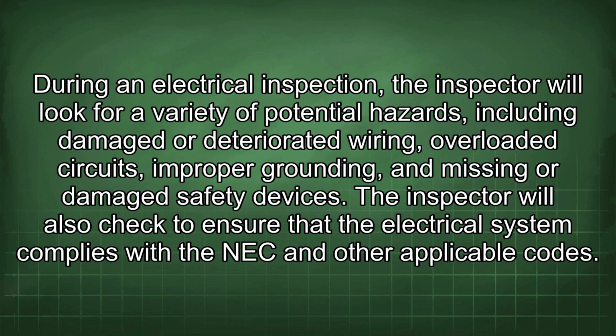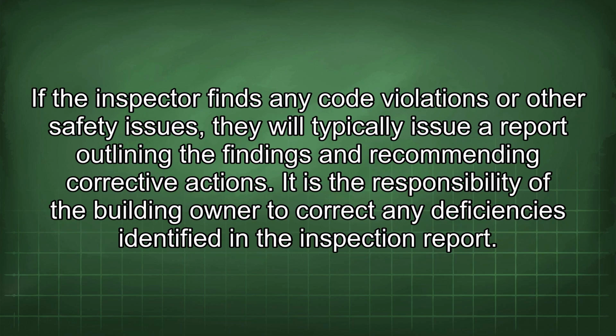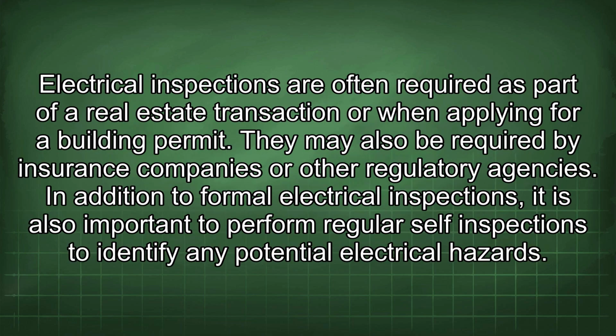During an electrical inspection, the inspector will look for a variety of potential hazards, including damaged or deteriorated wiring, overloaded circuits, improper grounding, and missing or damaged safety devices. The inspector will also check to ensure that the electrical system complies with the NEC and other applicable codes. If the inspector finds any code violations or other safety issues, they will typically issue a report outlining the findings and recommending corrective actions. It is the responsibility of the building owner to correct any deficiencies identified in the inspection report. Electrical inspections are often required as part of a real estate transaction or when applying for a building permit. They may also be required by insurance companies or other regulatory agencies.